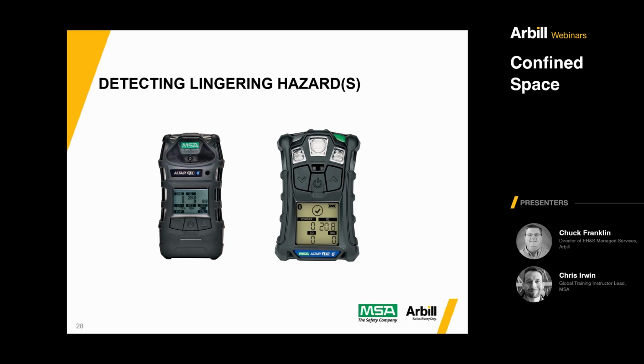Now I say this is a wearable device. So this one here, you would typically take in the space with you wherever it is that you might go. So imagine the 5X line is dropped right in at the entry portal, but you're walking horizontally away. This you can take with you as the entrant and see what the conditions are exactly where you are. That's not to say that you can't get a powered probe to attach to do testing from the outside. You can. It's just what I commonly find is a lot of times sites maybe originally got that piece and then have misplaced it, and now all they have is a detector.